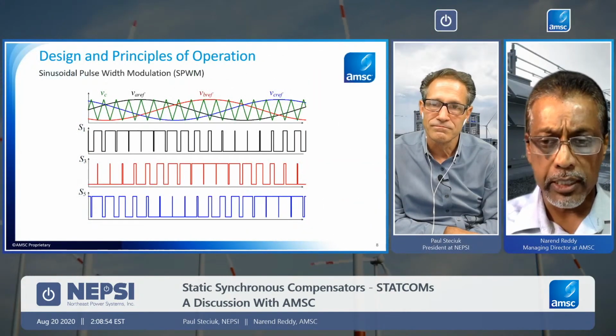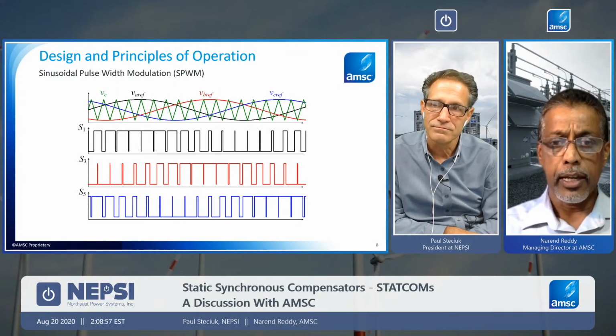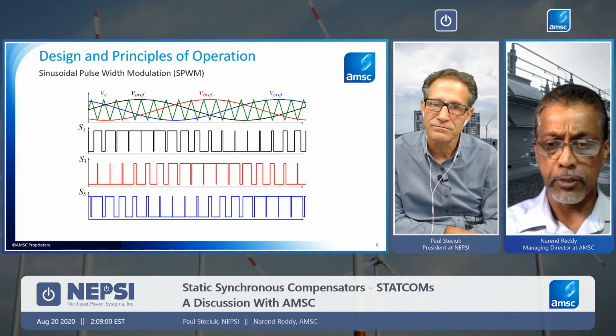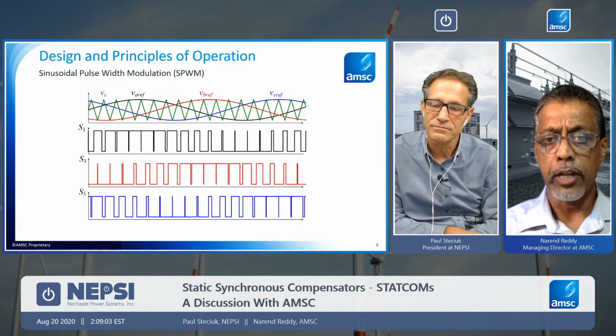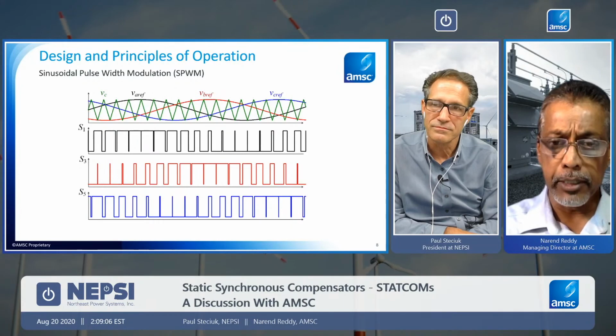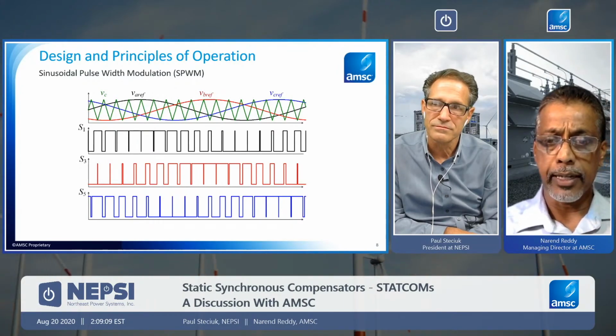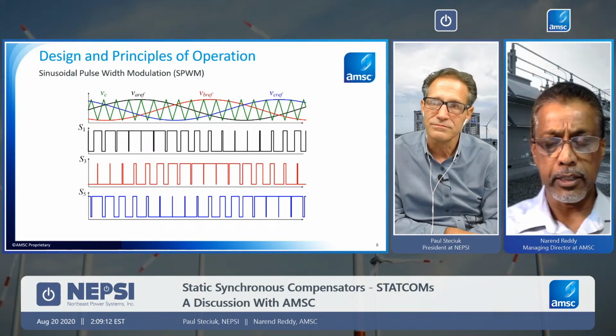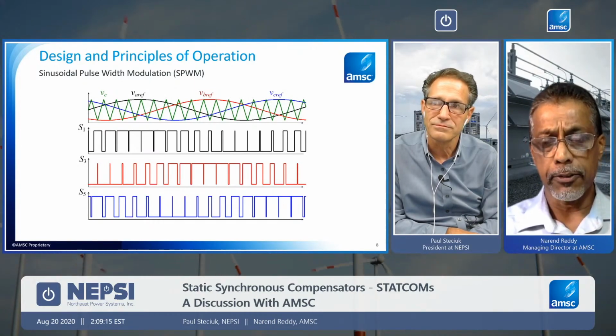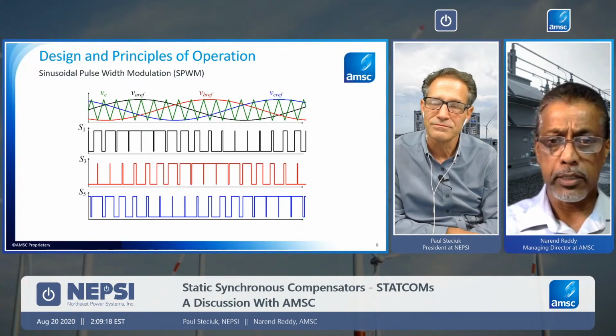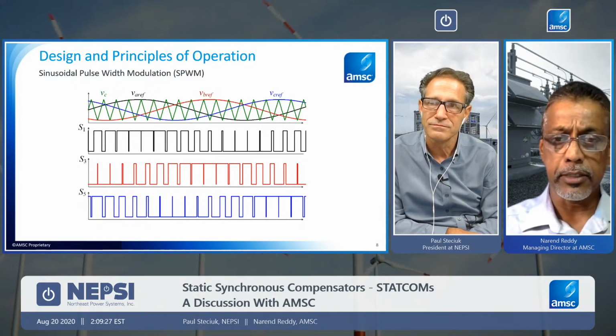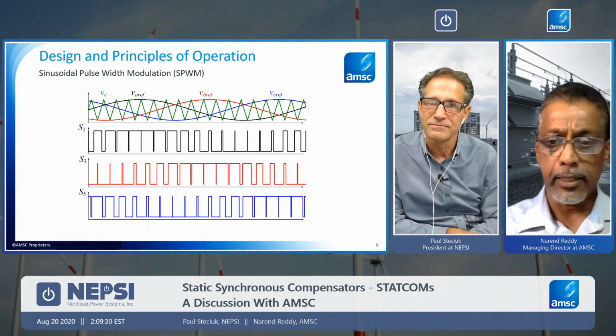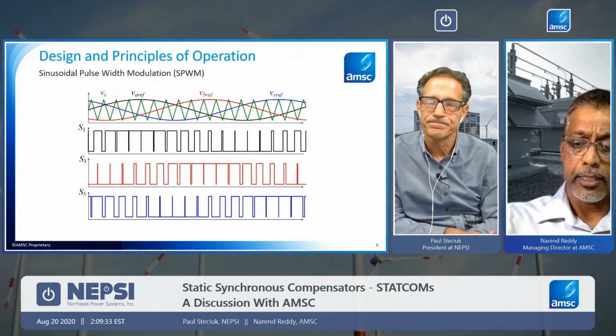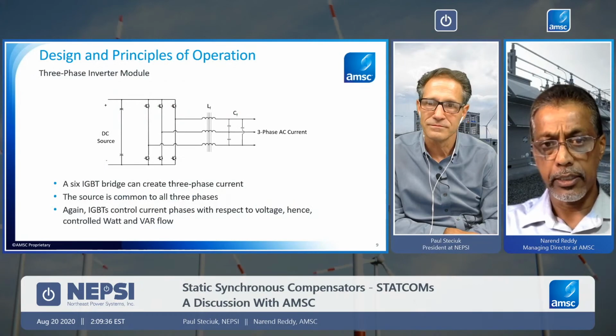So really, it's the switching of these IGBTs at a certain frequency, and that is at a very high frequency, usually in the 4 to 5 kilohertz range. And then basically the timing of how long the switching is maintained in the off state, or how long it is maintained in the on state, and the variability of it allows us to actually create a sinusoidal output current from this device, either at 50 or 60 hertz, depending on the system that it's connected to, and you end up with a nominal frequency current that is generated by the STATCOM or the inverters themselves.